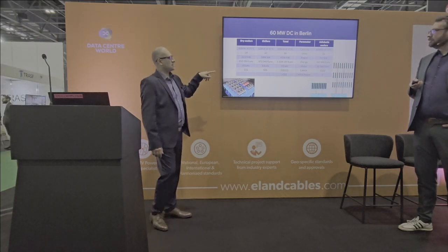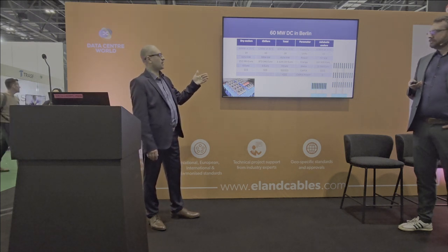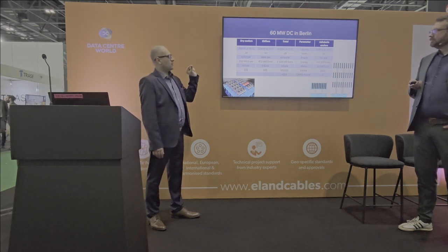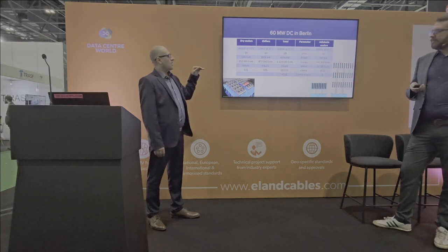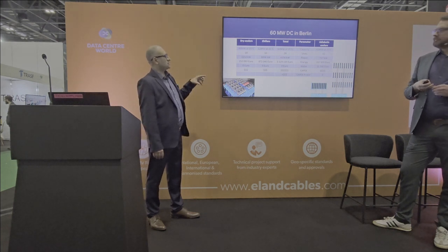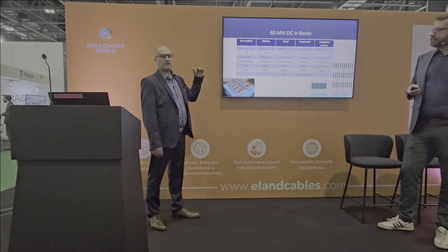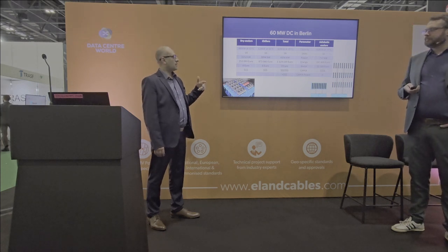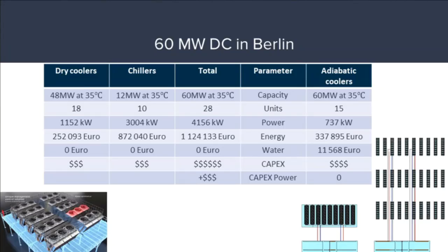And in this case, we see that we have savings on OPEX heavily. Instead of 1.1 million, we have just 0.3. And water consumption in money, it's negligible, so it's extremely low. But if we look for the CapEx, the chiller system with the dry coolers will be roughly for 2 million euro more. And plus on top of that, 3 million euros to cover this 3.5 megawatt power. So this is a comprehensive understanding of the cost of running system in our other traditional way.